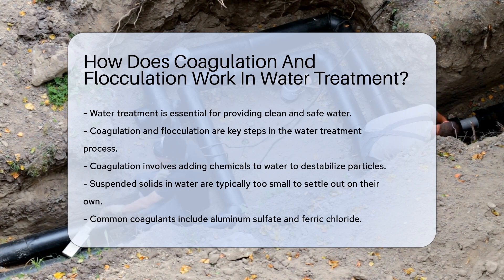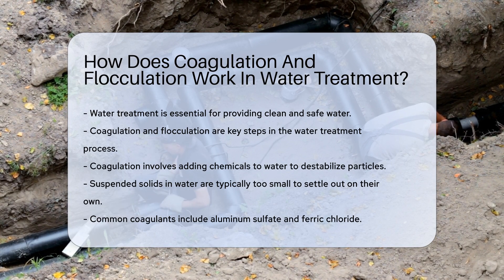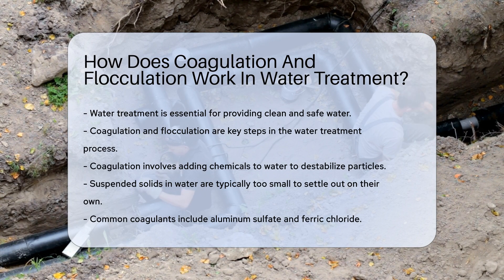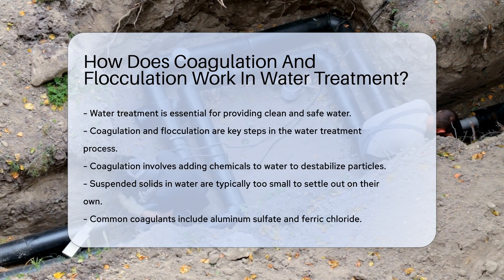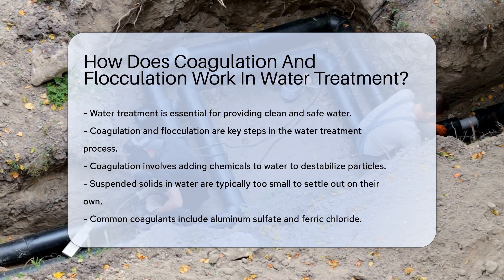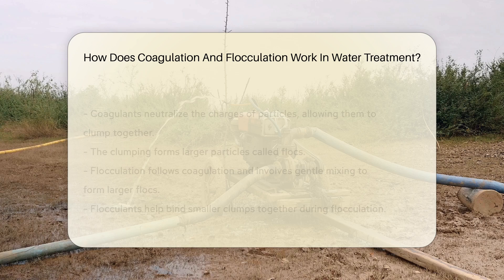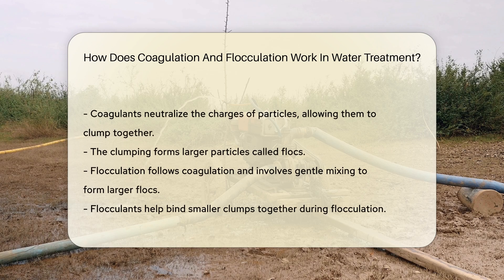Coagulation involves adding chemicals to water to destabilize particles. These particles are typically suspended solids that are too small to settle out on their own. Common coagulants include aluminum sulfate and ferric chloride. When added, these chemicals neutralize the charges of particles, allowing them to clump together. This clumping forms larger particles called flocs.